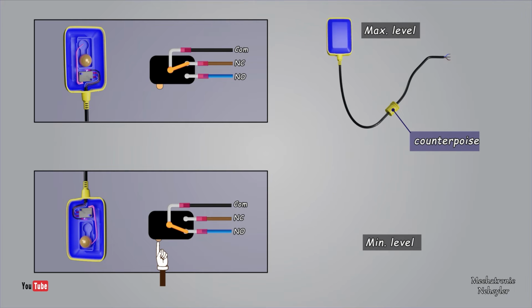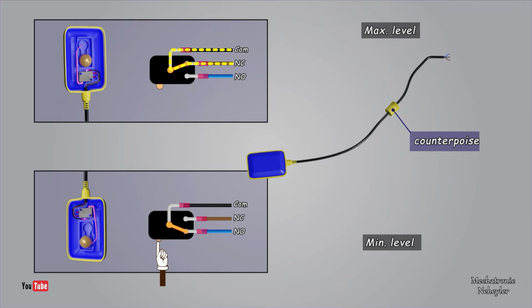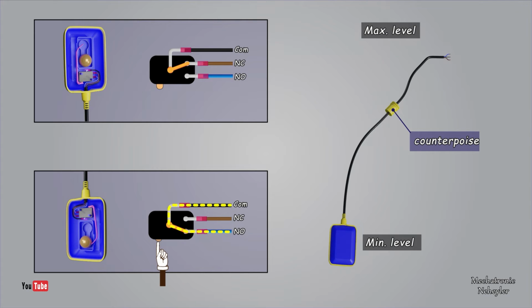This way, if the float is vertically up, current will flow through the common and normally closed wires. While, if the float is in a vertical downward position, the current will flow through the common and normally open wires. Taking these conditions into account, with the float in the minimum position, it must allow the electric pump to be turned on, then the black and light blue cables must be used. Since these also allow the electric pump to be disconnected when it reaches the maximum position.